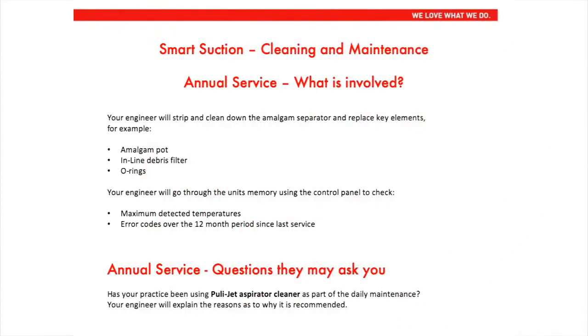Smart suction cleaning and maintenance. Annual service. What is involved? Your engineer will strip and clean down the amalgam separator and replace key elements, for example, the amalgam pot, the inline debris filter and O-rings. Your engineer will go through the unit's memory using the control panel to check maximum detected temperatures, error codes over the last 12-month period since the last service.